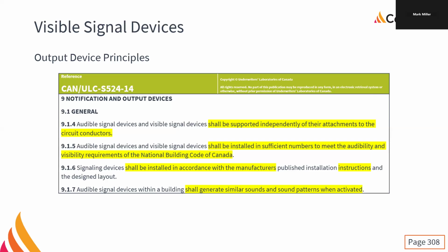The fire alarm system was done in 1989, and it badly needed to be redone. We did not remove any speakers. We reused all the speakers, but we also added 1,800 speakers to the building. It took quite some time, but we were looking at increasing audibility and intelligibility. But we'll talk about that when we get to speakers.